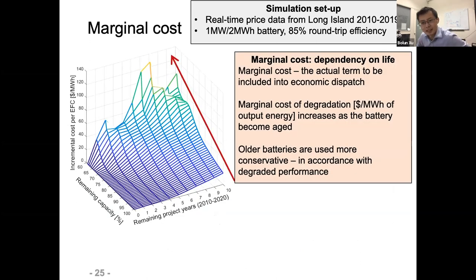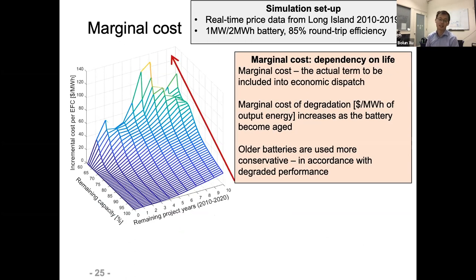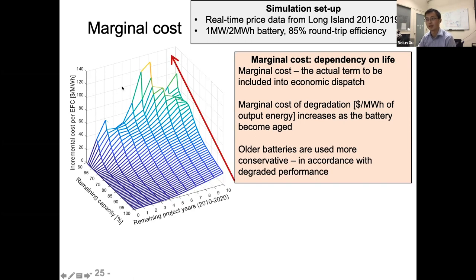Looking at the incremental degradation cost — the marginal cost, which is the derivative of the value surface — this is the actual term to plug into market optimization. It shows a very strong dependency of marginal cost on remaining battery capacity. A new battery has a marginal degradation cost around $0–$20/MWh, but as the battery approaches end of life the marginal cost jumps to five- or even ten-fold — up to over $100/MWh — and also becomes more sensitive to price dynamics.